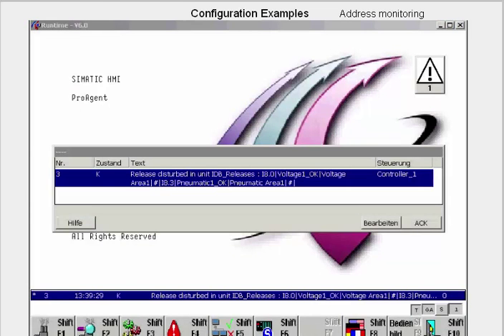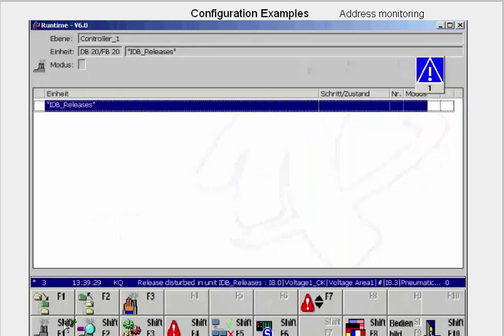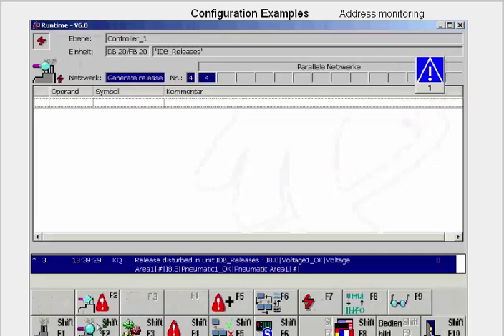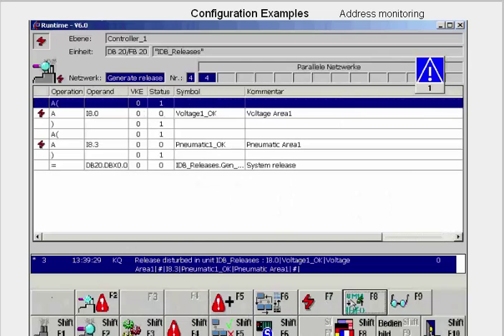As soon as a process fault is triggered for which monitoring has been configured, a pop-up window opens containing the configured message text. We acknowledge the message, switch to the message picture and to the detail view, where we can determine not only the addresses that caused the fault, but also the associated controller, the unit, and the network in which the fault occurred. With the F8 button, we can have the signals in the statement list network displayed.